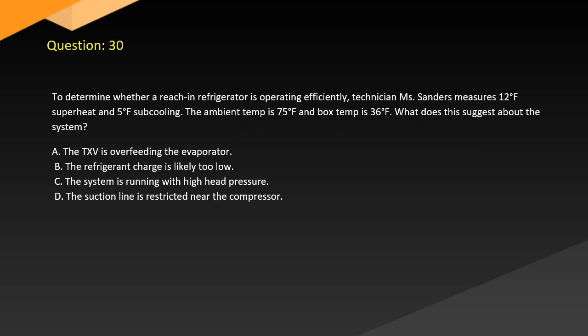Question 30. To determine whether a reach-in refrigerator is operating efficiently, technician Sanders measures 12 degrees F superheat and 5 degrees F subcooling. The ambient temp is 75 degrees F and box temp is 36 degrees F. What does this suggest about the system? A. The TXV is overfeeding the evaporator. B. The refrigerant charge is likely too low. C. The system is running with high head pressure. D. The suction line is restricted near the compressor.